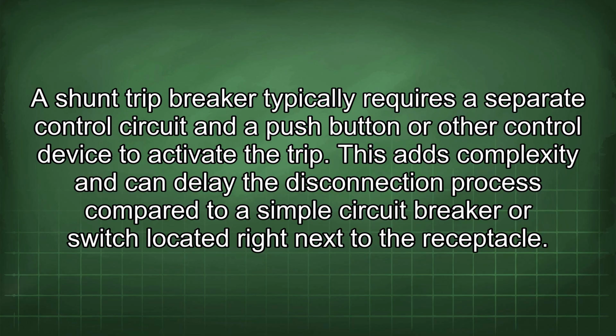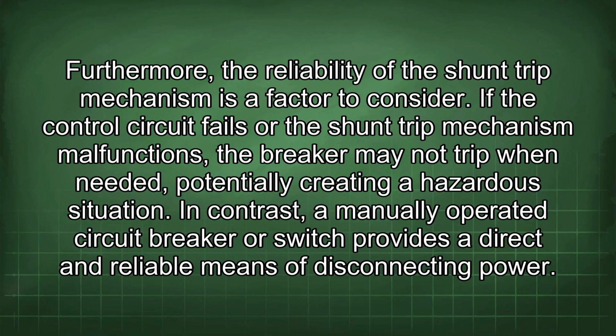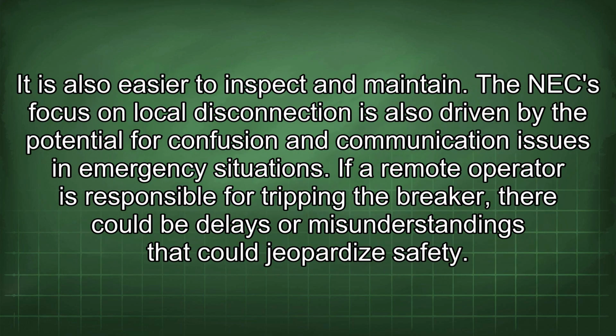A shunt trip breaker typically requires a separate control circuit and a push button or other control device to activate the trip. This adds complexity and can delay the disconnection process compared to a simple circuit breaker or switch located right next to the receptacle. Furthermore, the reliability of the shunt trip mechanism is a factor to consider. If the control circuit fails or the shunt trip mechanism malfunctions, the breaker may not trip when needed, potentially creating a hazardous situation. In contrast, a manually operated circuit breaker or switch provides a direct and reliable means of disconnecting power. It is also easier to inspect and maintain.